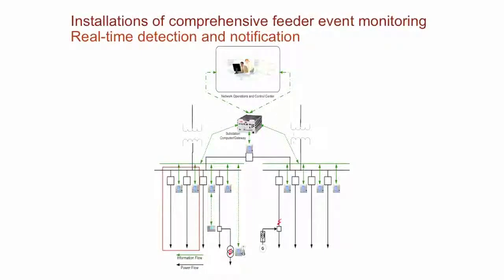But because of how we're going to monitor - this is an example - we can even increase the asset scope because we want to go into the point of common coupling with DG, distributed generation. Since it's Denver, that would be PV, photovoltaic. So we have a connection point - our goal is to have a connection point with intelligent equipment at the point of common coupling where the solar panels connect into the feeder.